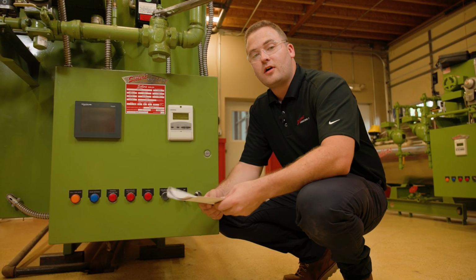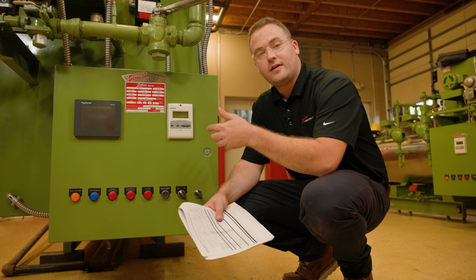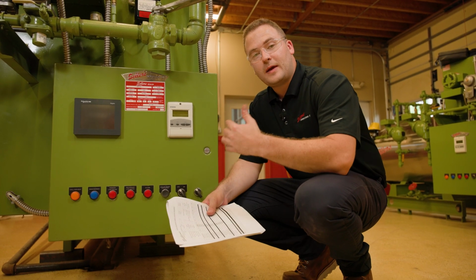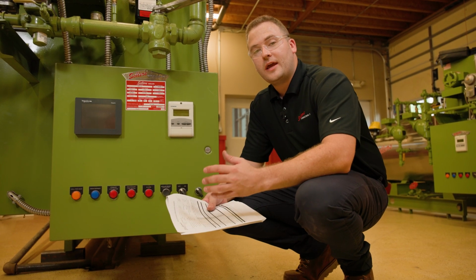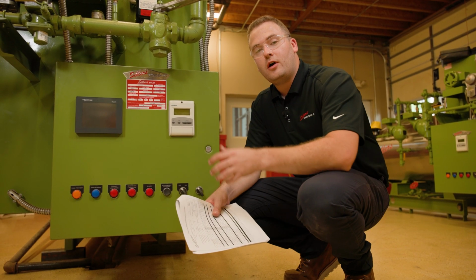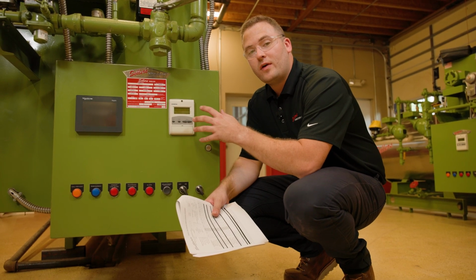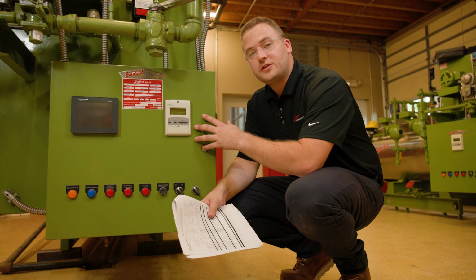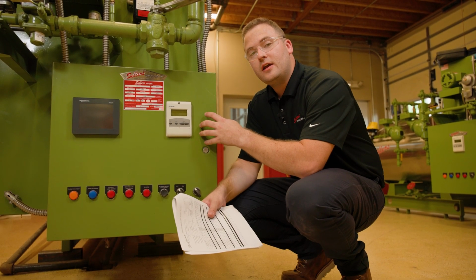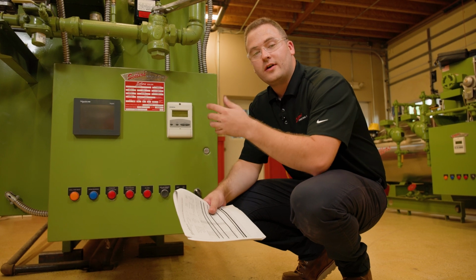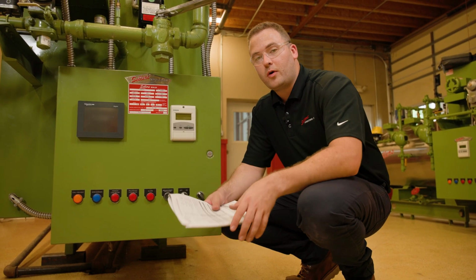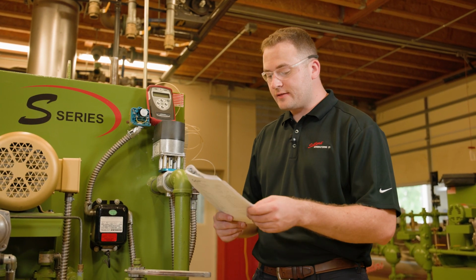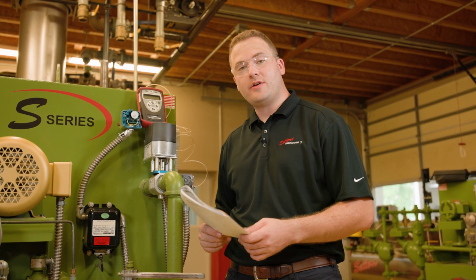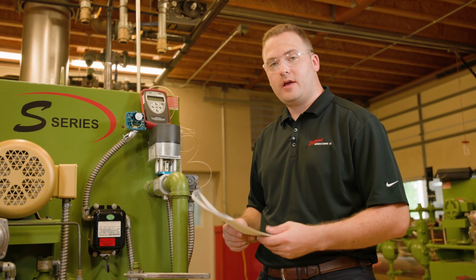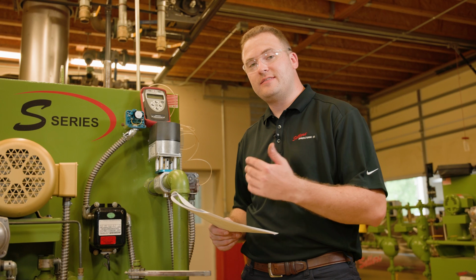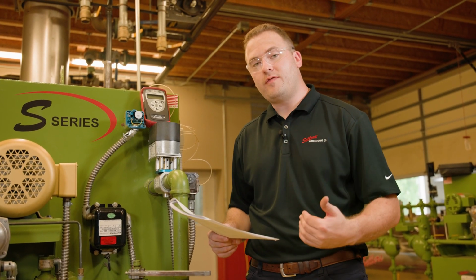For a customer installed boiler, the installation is going to be slightly different than the Sellers Manufacturing site, especially if you have a higher elevation. So you're going to want to make sure that you are always checking the air-fuel ratio of the boiler. Sellers Manufacturing, when they test fired the boiler, they've set the fuel pressure and the fuel valve settings to be metered. So you should only have to make air damper settings when you're making your final adjustments for your installed boiler. The next line of the factory test record is going to be your input. That is your gas input that the factory has metered for the gas flow input to the burner. You're normally not going to change this, as the factory has set this up so that you have the proper high fire and low fire turn down settings.